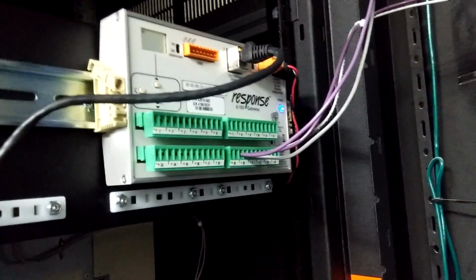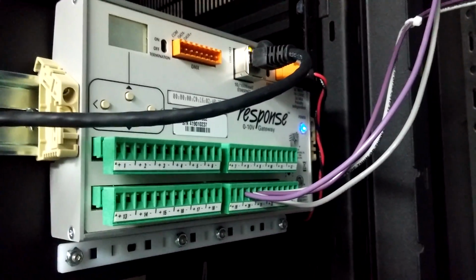We have our ETC Response 0 to 10 volt gateway, because we have a couple 0 to 10 volt fixtures in this space as well. So this takes streaming ACN and converts it to a 0 to 10 volt signal for those lights.